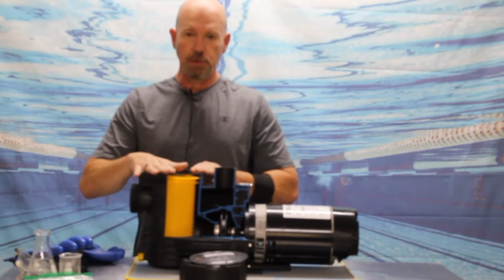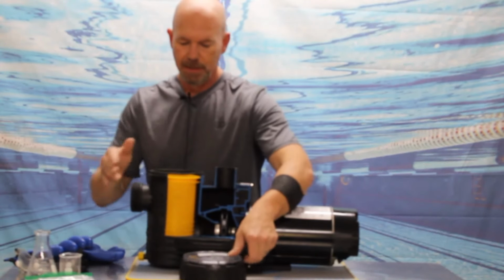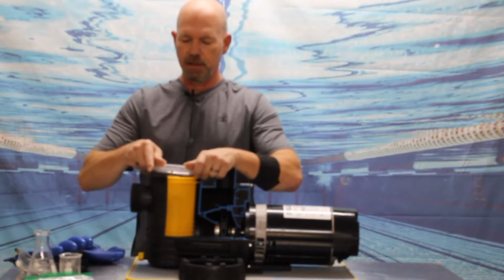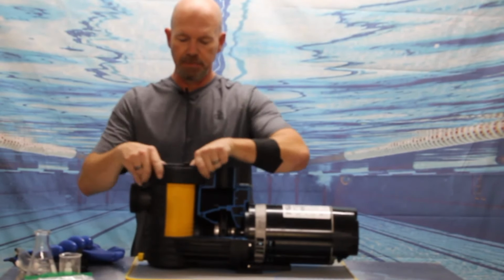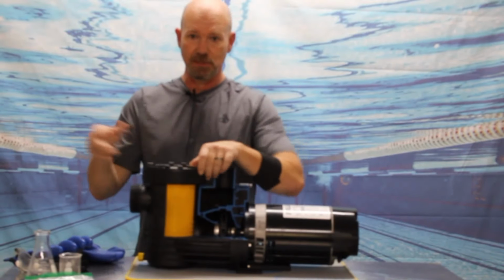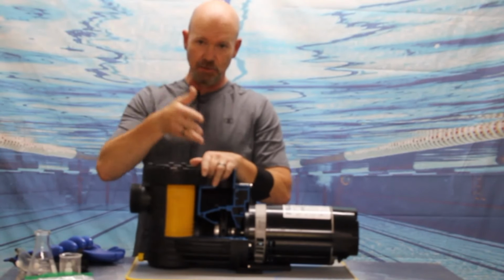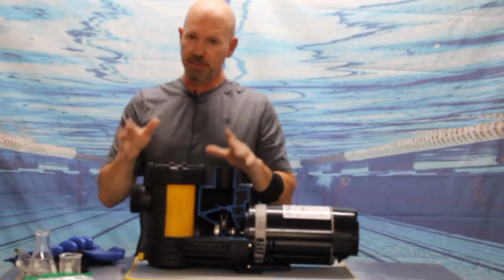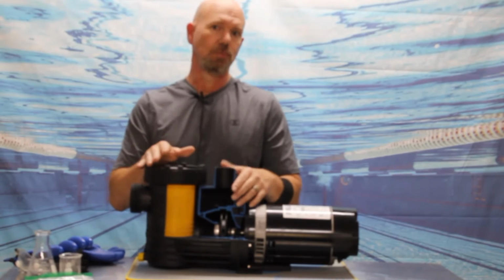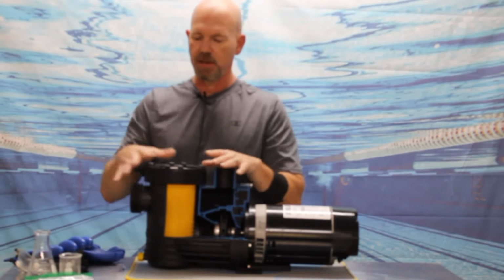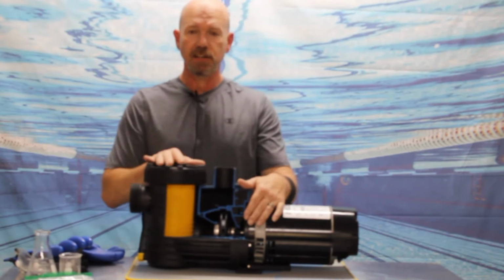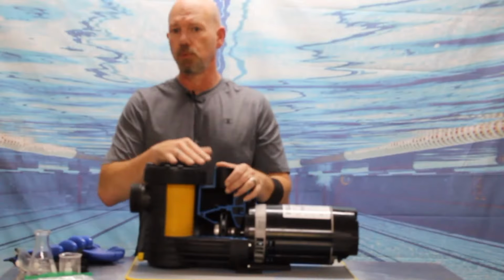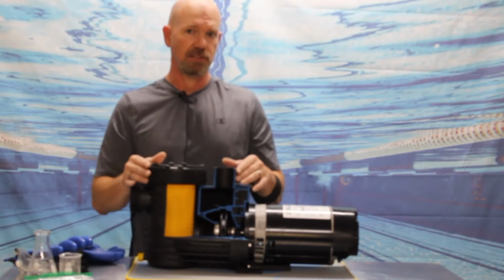But if we've had to replace it, or it's the same one, and we're still seeing the issue, the next thing I want to check is my mechanical seal, my pump seal. Now, I said there was one exception to drawing in air and dripping water. The pump seal is the only point that will actually do both, draw in air and drip water. Every other place that you can have a suction side leak will only draw in air. The pump seal is also the furthest point back in the system where you can have a suction side leak.